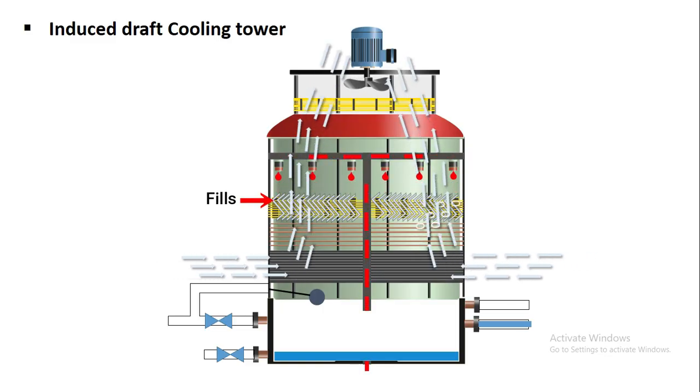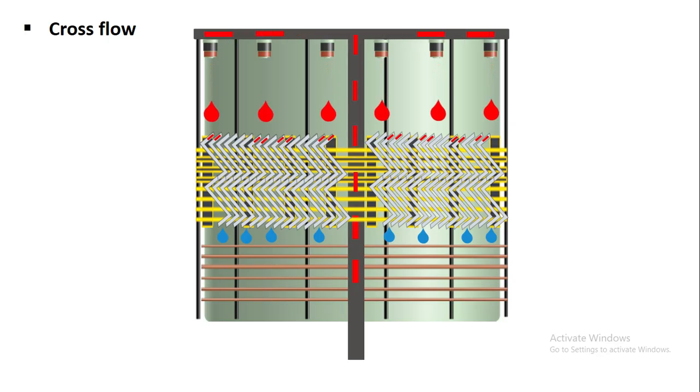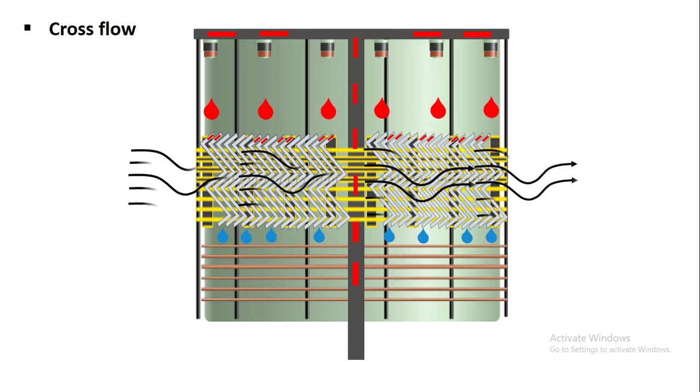Depending on how the air enters there are two main designs, cross flow and counter flow. In the cross flow towers air flows horizontally through the fills while water flows vertically downward. This means the air and water paths cross at right angle directions. The main advantage of cross flow cooling tower is lower pumping head is required because water is distributed by gravity.